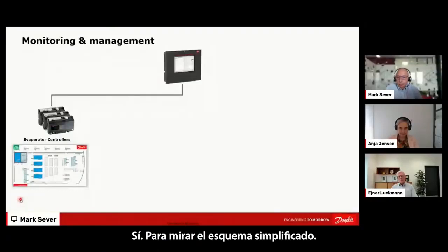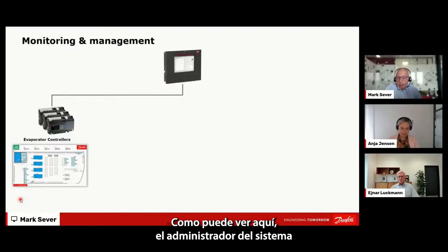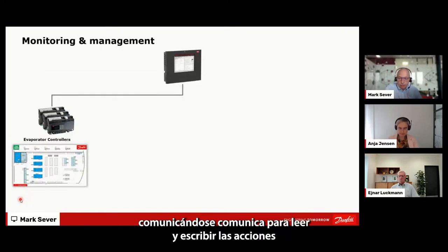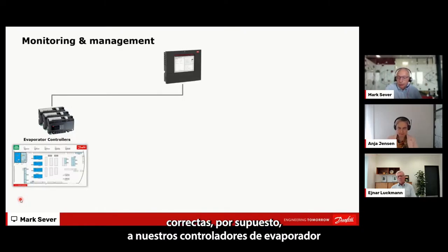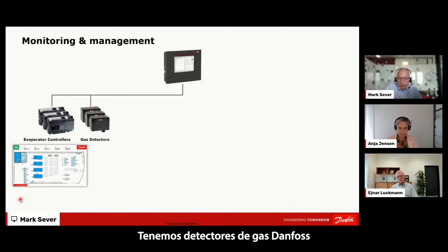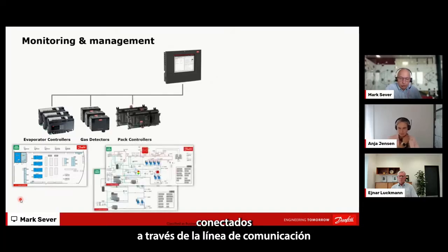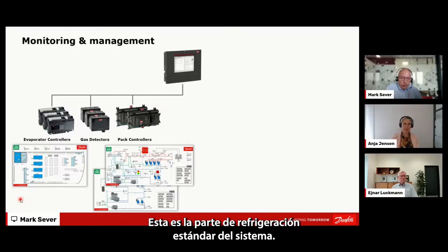To look at a simplified scheme, as you can see here, the System Manager is communicating with read and write possibilities to our evaporator controllers. We have Danfoss gas detectors connected through the communication line to the System Manager and also the pack controllers. So this is, let's say, the standard refrigeration part of the system.